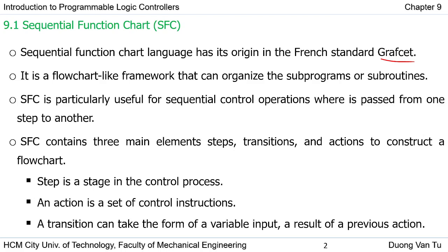The SFC language contains three main elements. The first element is the step — the state of the control process. For example, in the mixer system, filling the material is a state of the control process, or mixing the compound is also a state. So we define a step as a state in the control process. The second element is the action — a set of control instructions, meaning the content for every step. In each step we implement something, like turning on a lamp or turning on a valve.